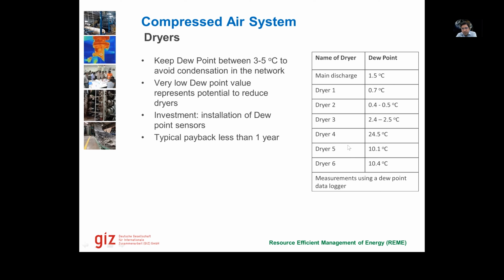We got them repaired, and then we requested the factory to maintain this between 3 and 5 degrees Celsius. So with the same amount of compressed air at full load, now they are only running the first 4 dryers, and the remaining 2 dryers are totally on standby. All they had to do was install some humidity sensors and a dew point sensor in the main line, and the typical payback for these sensors is less than 1 year, actually, even half a year.